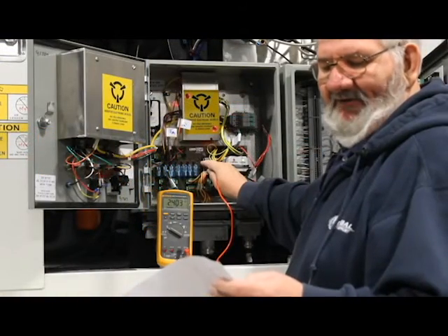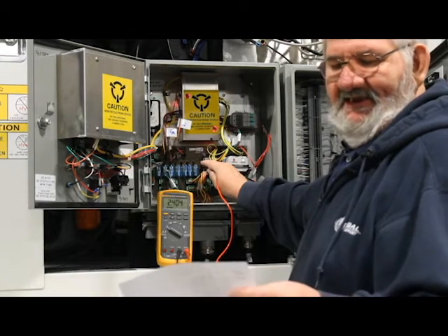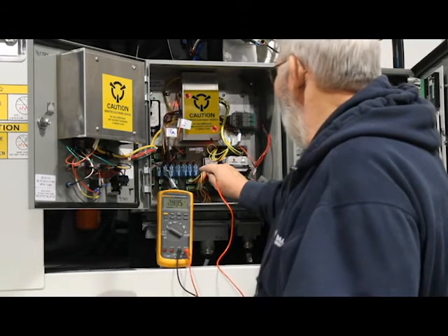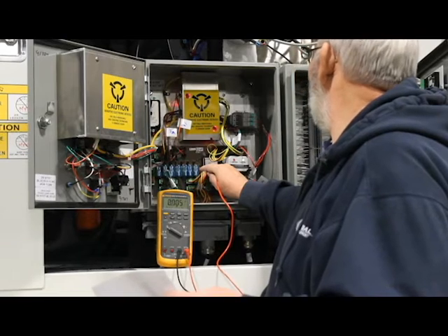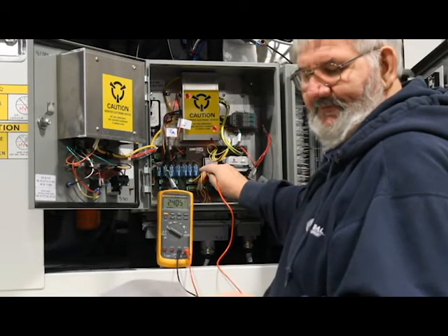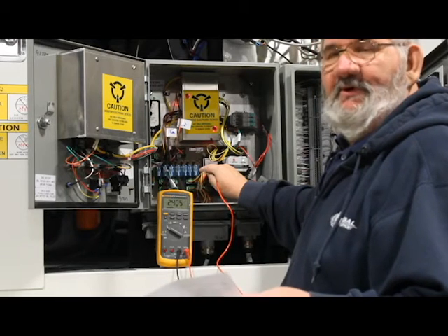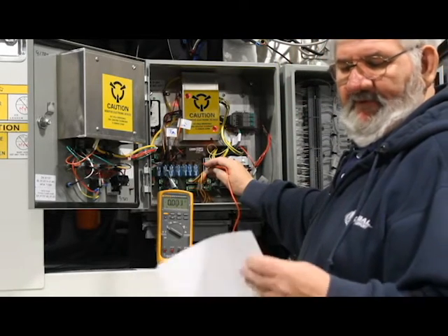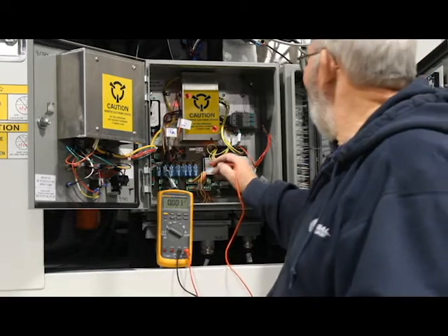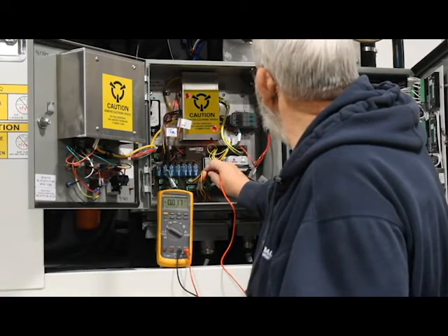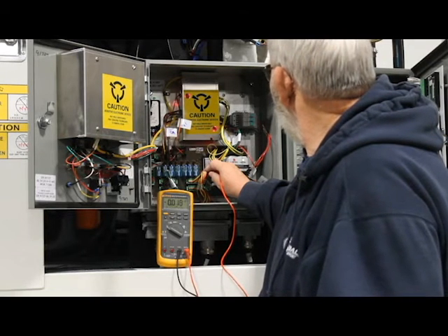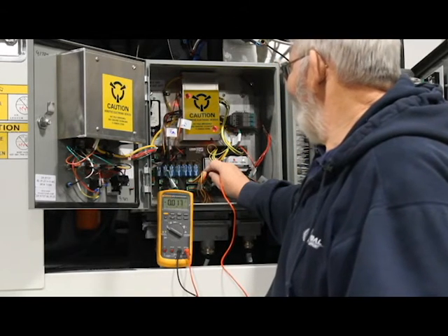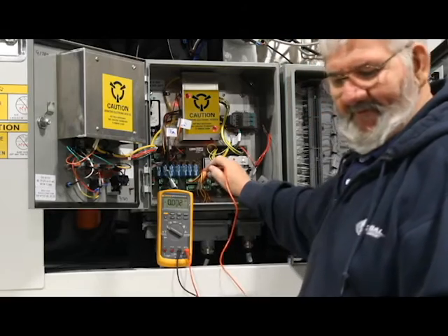You can go to your inlet RTD, which is test point number 8, right here, and it will measure the same, 2.4 volts. Here again, it ranges between 1 to 5 volts. The same thing with your fuel pressure transducer, which is test point number 10. Down here, you can simply measure it. We have just right about 0 voltage on your fuel pressure transducer.